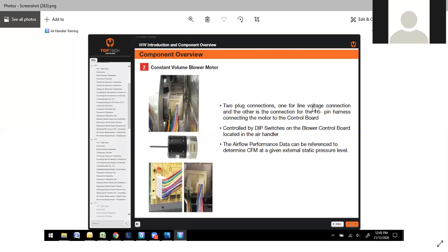So you have two plug connections, one for line voltage and the other is for the 16-pin harness connecting to the motor control board. So your single pin is going to be your line voltage. There again, that should always be live. If you do not have 208 or 230 to that, then you have to determine why that is. This is always live.